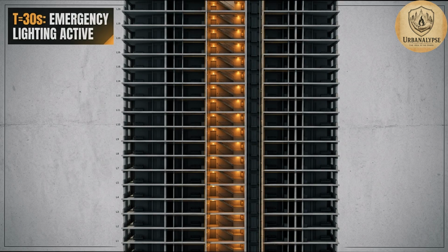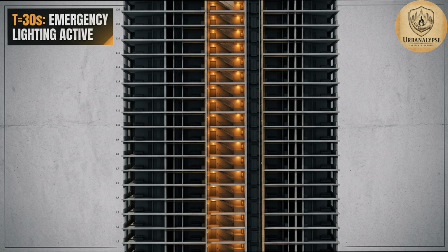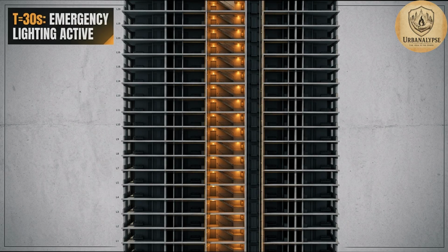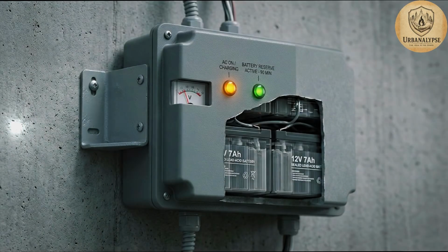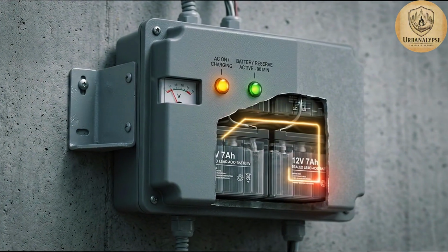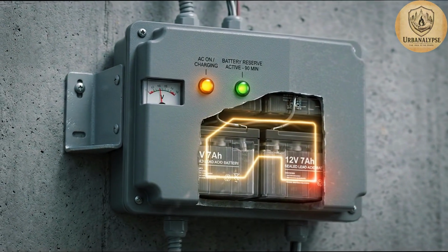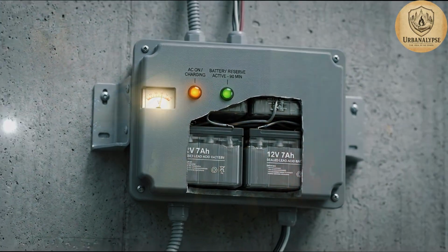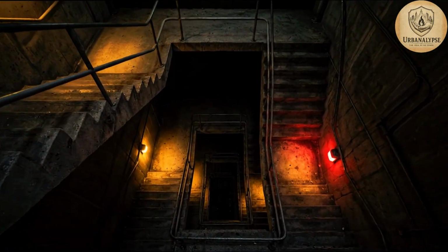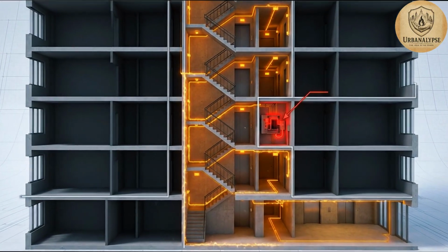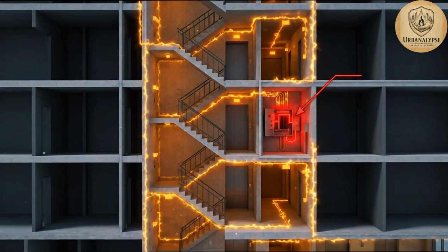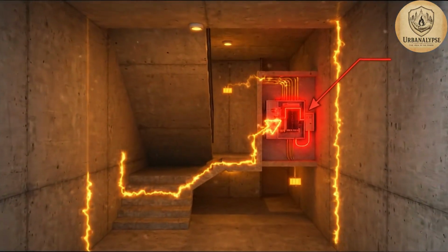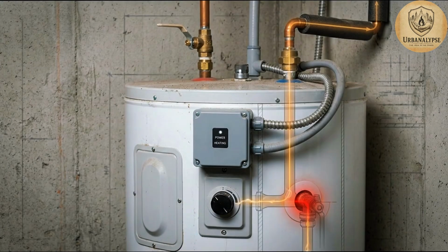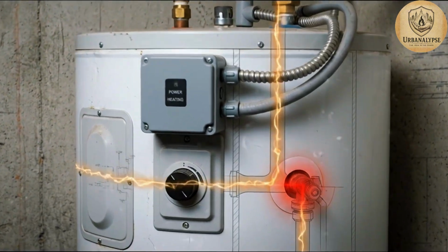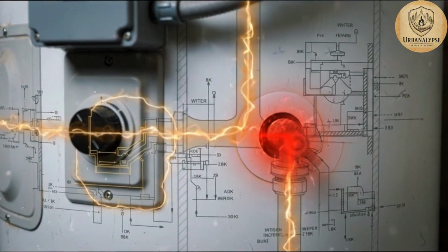From T30 seconds to roughly T3 minutes, battery-backed emergency lighting activates on its own dedicated circuit, required under NFPA 101 Life Safety Code, to sustain illumination for a documented minimum of 90 minutes on stored charge alone, independent of any generator start sequence. That circuit covers lobbies, stairwells, and exit signage only, never apartment units, never HVAC compressors, never your hot water heater. Your unit's outlets stay dark because they were never wired onto that emergency branch. The branch exists strictly for egress, not for comfort or convenience.